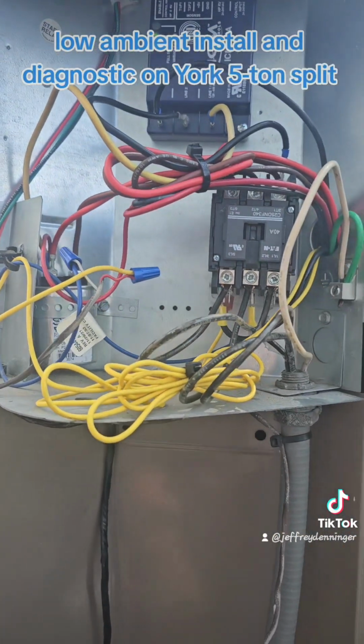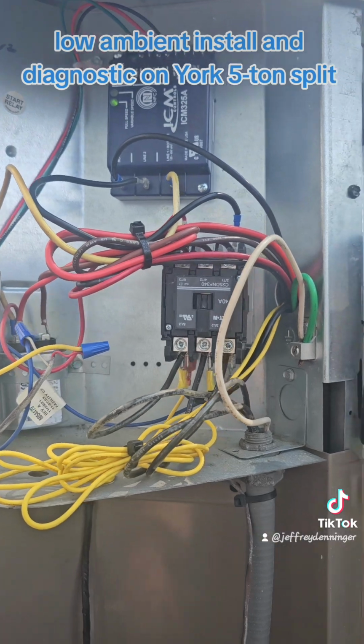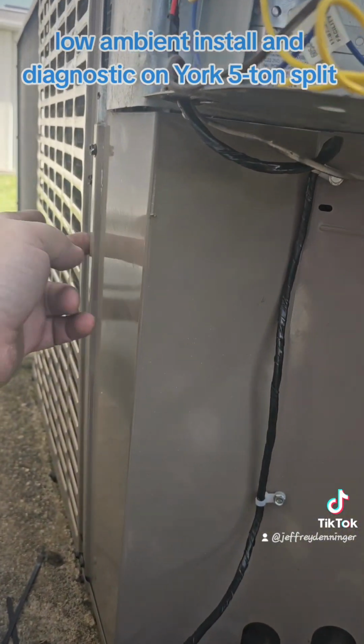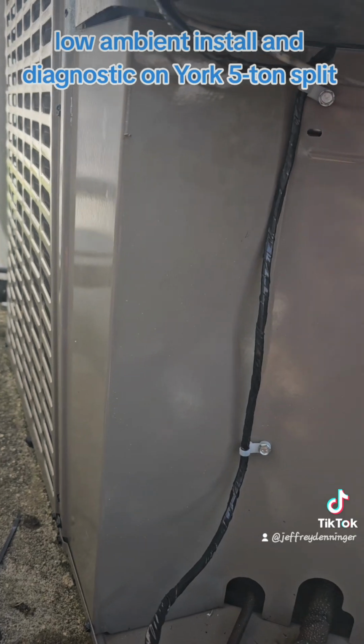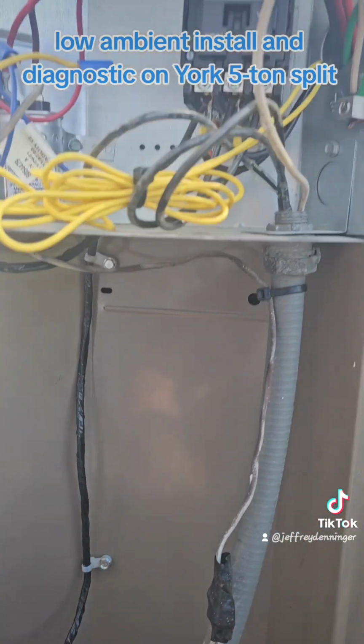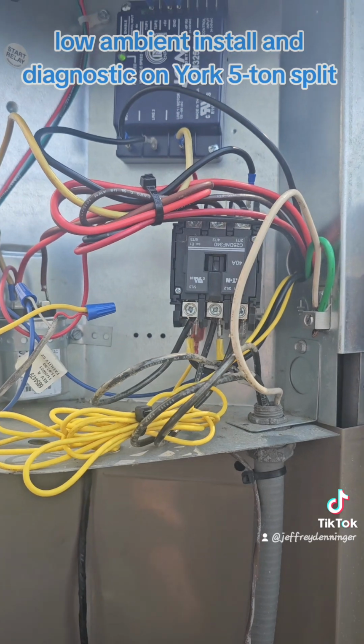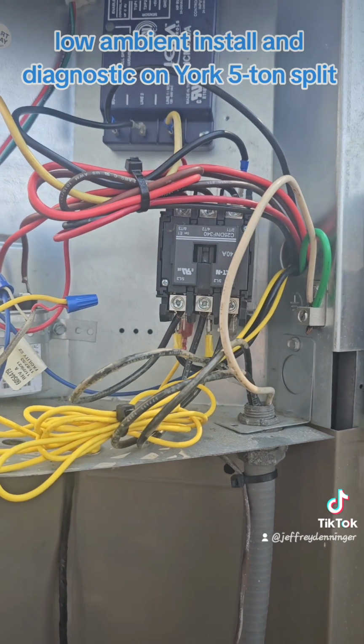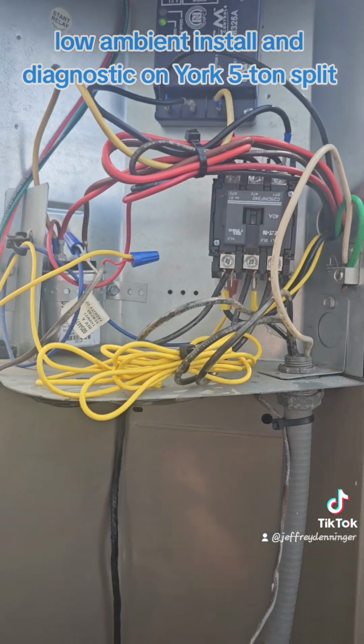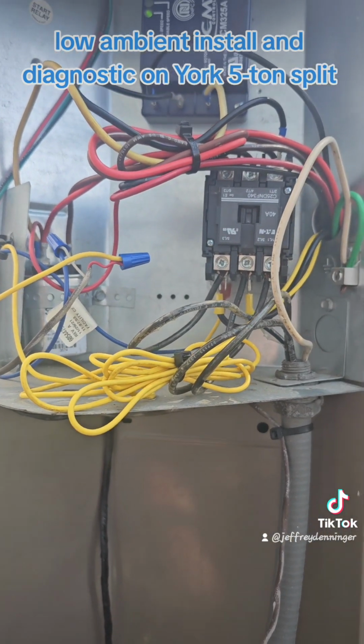Outside air condenser, upon arrival, system was not functioning correctly. We found a restriction in the coil while trying to put in the low ambient kit for this. So we had to come back this morning.